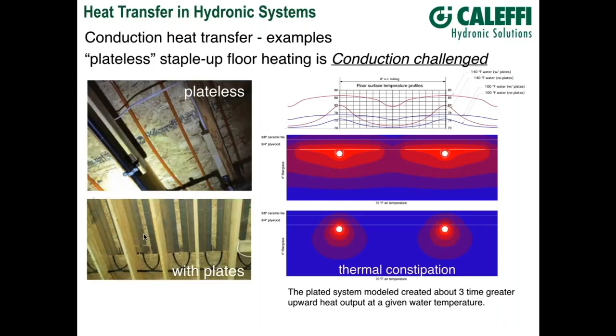We modeled this with finite element analysis software. The graphics show different regions from red through various shades out to blue, representing bands of temperature. It's very obvious that the plate — even though it's a thin plate on the order of 20 thousandths of an inch — aluminum has a high thermal conductivity, so it acts like a wick. It diffuses heat out away from the tubes and spreads it across the floor, which is very important for achieving a consistent floor surface temperature.